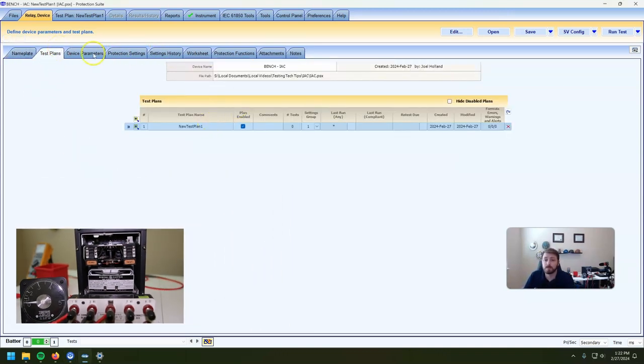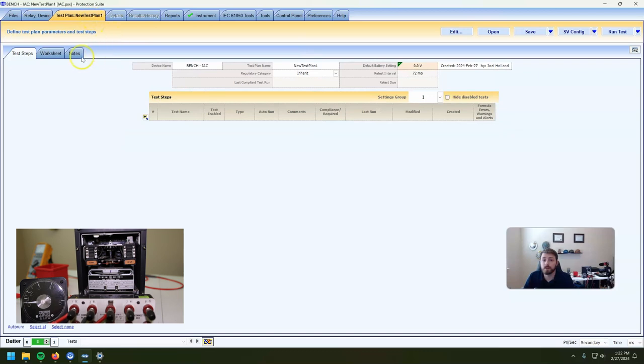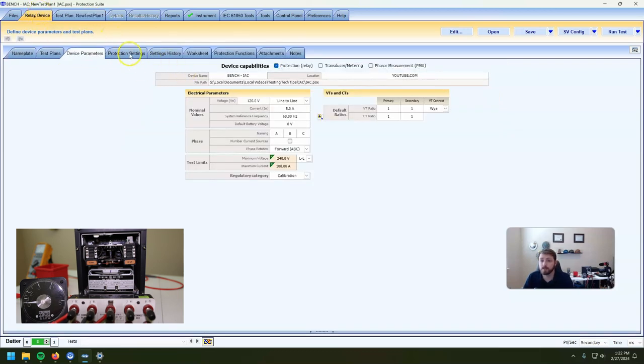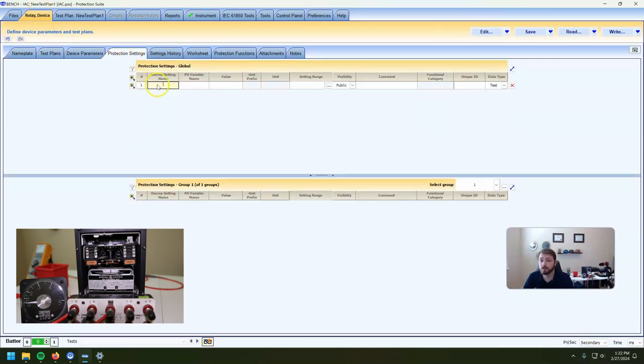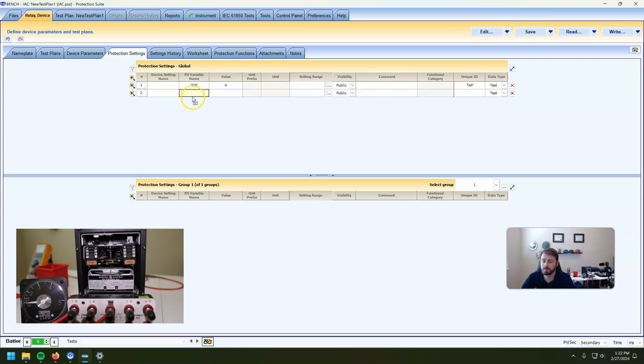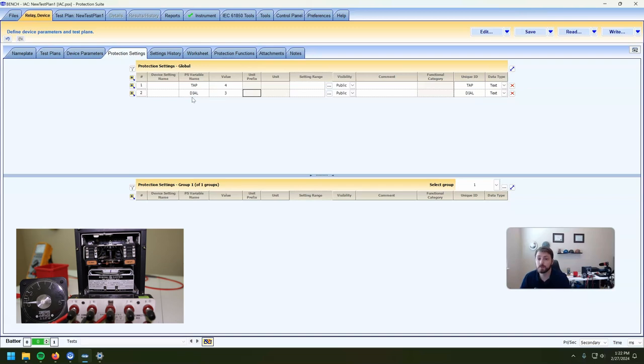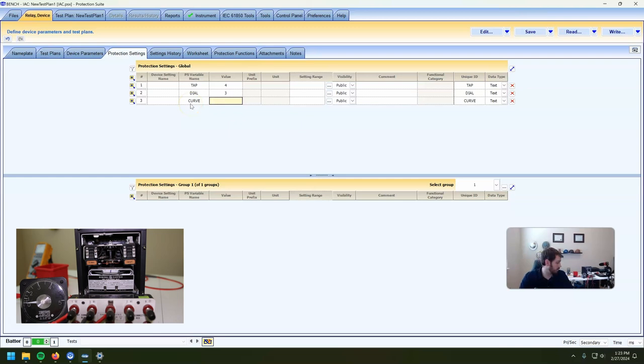Make a new test plan. Let's go ahead and put our settings in. I change the tap down to 4 — that's our minimum pickup, so our tap is 4. Our dial, the time dial, is set to 3. And then our curve — this is a 53B curve.